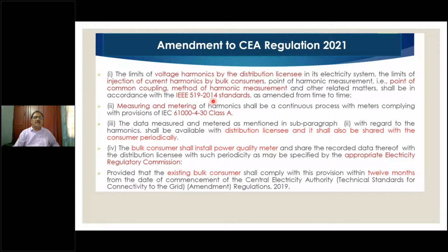The second thing is, in the amendment, CEA also spoke about measuring meter and measuring methods as prescribed under IEC 61000-4-30 Class A. They have carefully omitted edition 3, which is the latest edition. And even if they have omitted edition 3, as per the standard, edition 2 is null and void. Those of you who are interested in pursuing this particular topic can ask me to share more information with you.